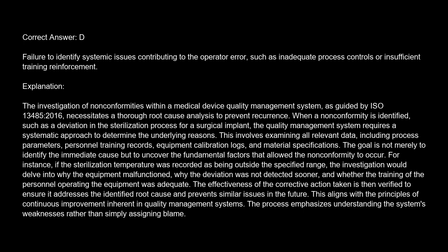insufficient training reinforcement. Explanation. The investigation of nonconformities within a medical device quality management system, as guided by ISO 13485-2016, necessitates a thorough root cause analysis to prevent recurrence. When a nonconformity is identified, such as a deviation in the sterilization process for a surgical implant, the quality management system requires a systematic approach to determine the underlying reasons.